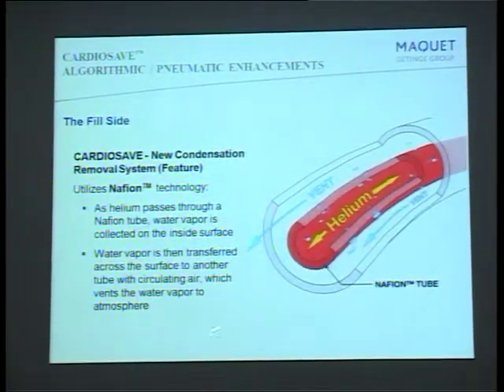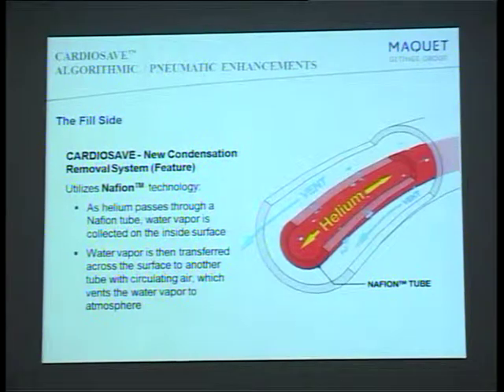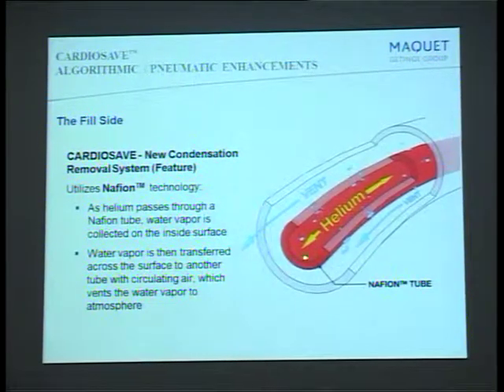But in CardioSave, in this machine, you don't have a CRM — there is no condensate removal module. Instead, we are using a technology called Nafion technology, where the helium passes into the Nafion tube and the vapors are ejected automatically.